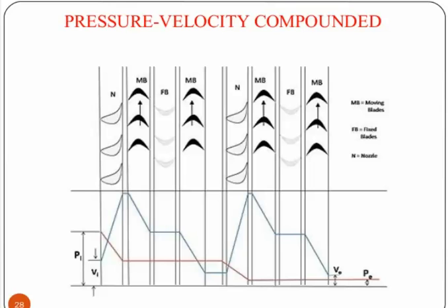The fixed blade acts as a nozzle and the steam coming from the boiler is passed to the first ring of fixed blade, where it gets partially expanded, the pressure partially decreases and the velocity rises correspondingly. The velocity is absorbed by the following rings of moving blade until it reaches the next ring of fixed blade, and the whole process is repeated once again.